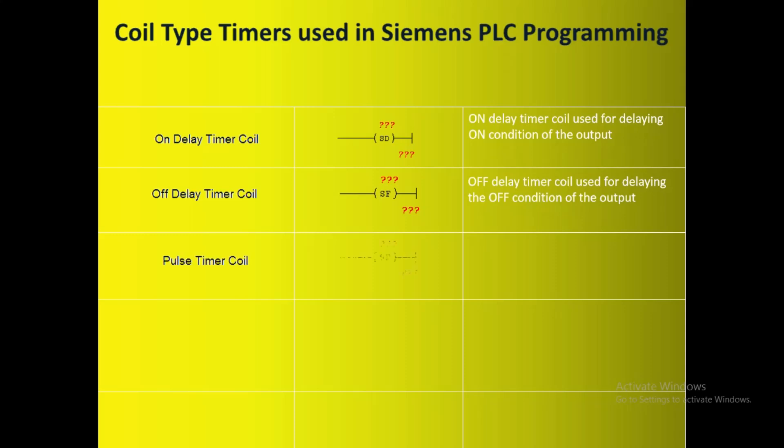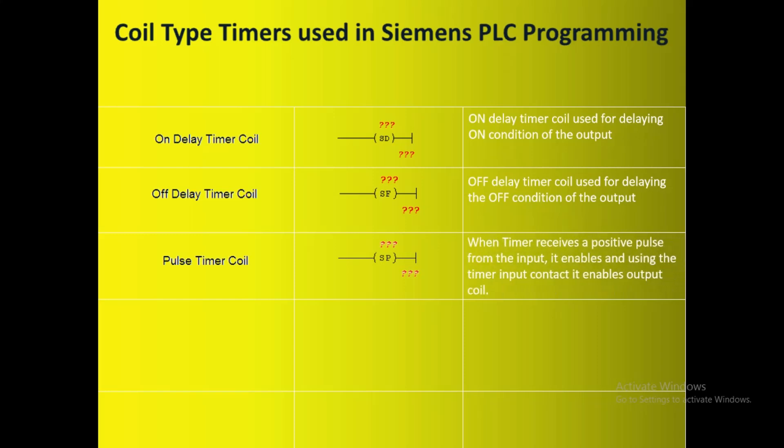The next one is the Pulse Timer Coil, and this is the notation used in PLC for this timer. When the timer receives a positive pulse from the input, it enables the output coil. The timer remains in the on condition as long as the input condition is on or the accumulator value reaches the preset value. If the input changes from one to zero before the timer interval has elapsed, the timer stops along with disabling the output. A reset coil from the bit instructions needs to be used separately to reset the timer.